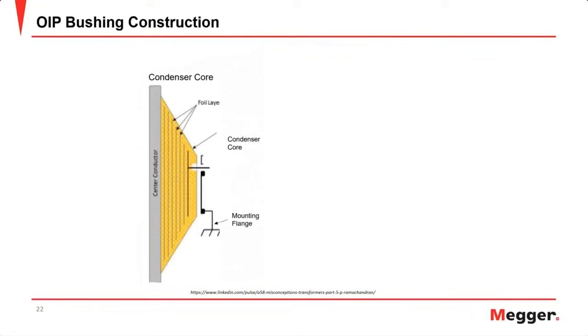So what we'll focus on now is mainly OIP bushings and how they are constructed. Within the center of the bushing, you will have the conductor that runs through, and then this capacitive graded bushing will have layers of insulation and then foil to help break down that voltage before we get to the tap that comes off the side. And the tap is there for a couple of reasons. One is to help determine the health of the bushing, and another one is that if you have a voltage or potential tap, you can use that during bushing monitoring while the transformer's in service, or partial discharge testing, or online measurements. So it's used to get that voltage down to a usable level when it comes to either instruments that are online or offline.